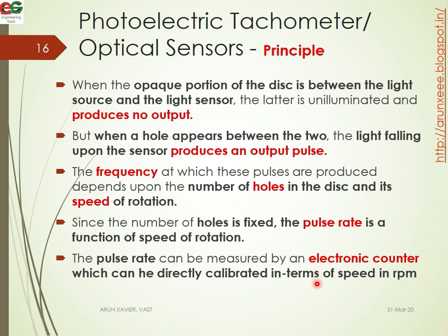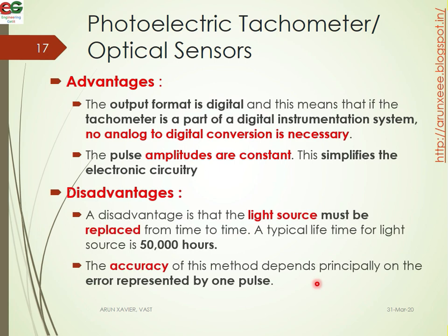The pulse rate can be measured by an electronic counter which can be directly calibrated in terms of RPM. The advantages are that the output is in digital format, so no analog-to-digital converter is necessary and the pulse amplitude is constant, simplifying the electronic circuitry. The disadvantage is the problem with the light source — it has a limited life and needs to be replaced. The accuracy depends on the error represented by one pulse.